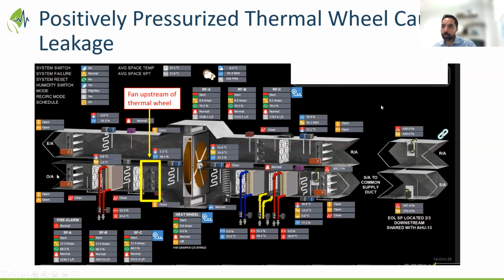And in one hospital, because of that, a lot of snow is being pulled in because the unit is running at a higher velocity. The dampers or louvers are not sized for the higher velocity, which generates that entrainment of snow, which builds up on the cooling coils or heating coils and hinders the performance of the wheel indirectly, because now you have to run the preheat coil at a higher temperature to melt that snow and other issues.